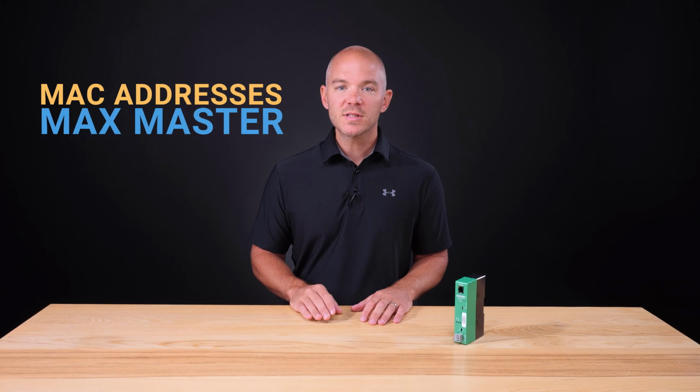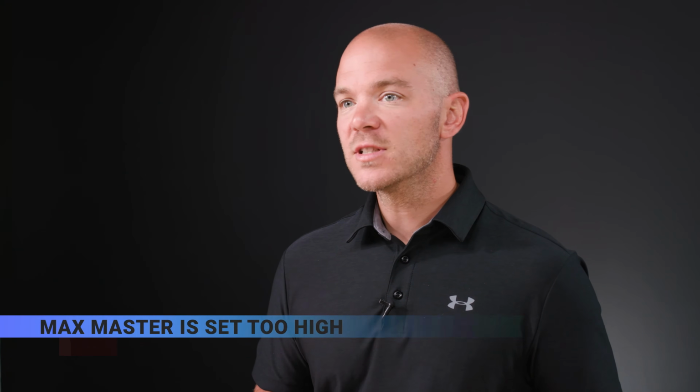There are many things that cause a BACnet MSTP network to function slowly and inefficiently. In this series of videos, we're discussing common mistakes that people make and ways to solve them. Let's look at problems with MAC addresses and max master. One common problem occurs when max master is set too high.